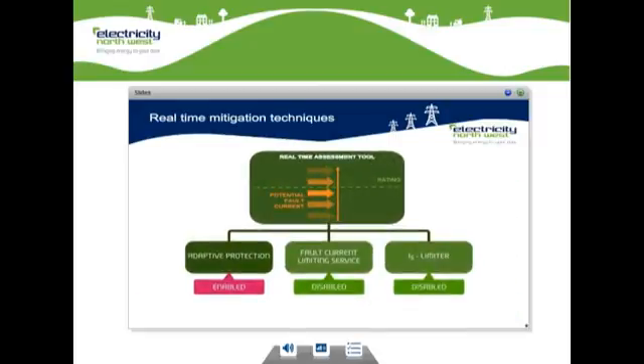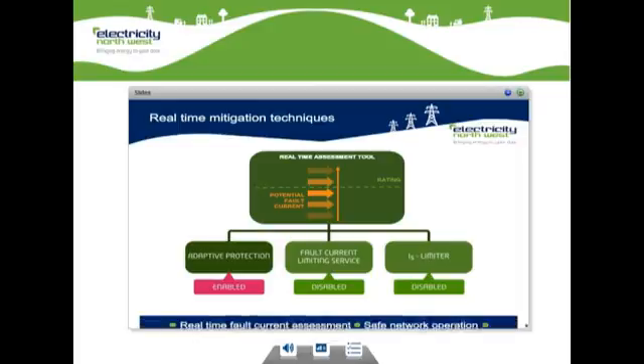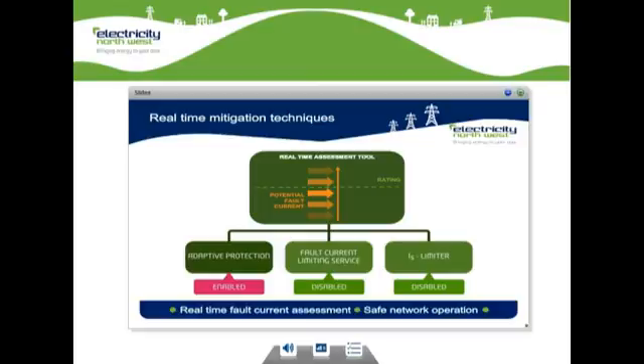When fault level approaches or rises above the fault level rating of network equipment, the Fault Level Tool will notice this and will be able to enable one of three innovative techniques designed to manage fault current. The techniques are adaptive protection, the fault current limiting service, and the IS limiter. All three techniques, when enabled, respond after a fault occurs, reducing fault current so that every item of network equipment operates safely.